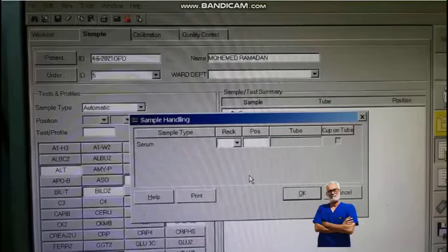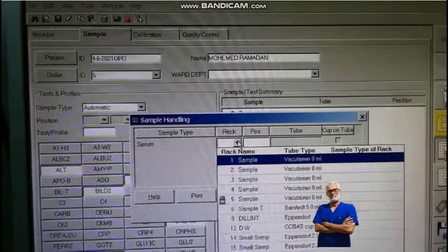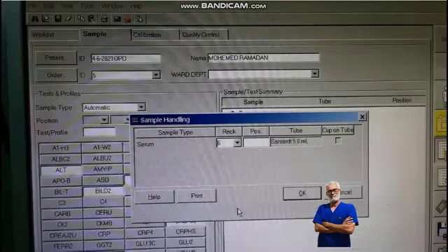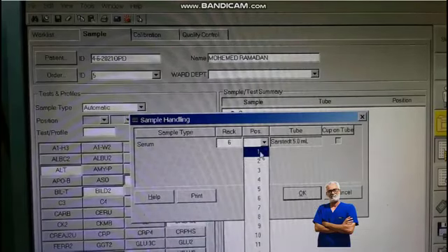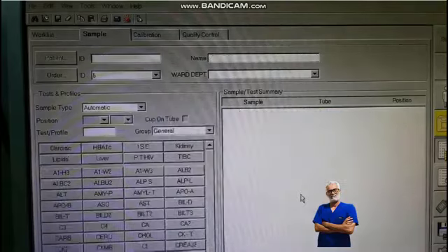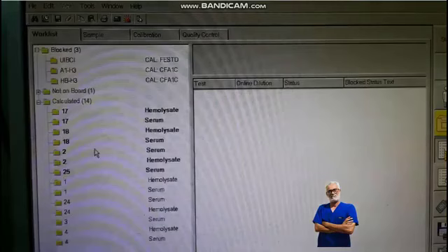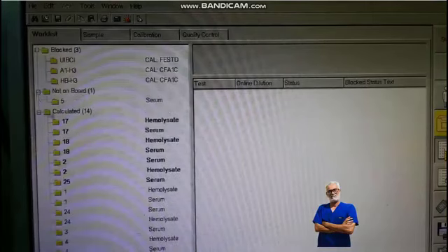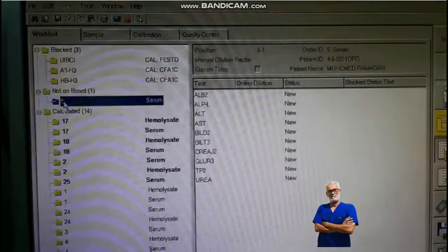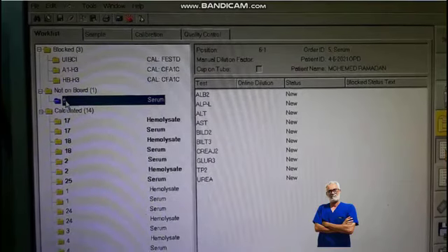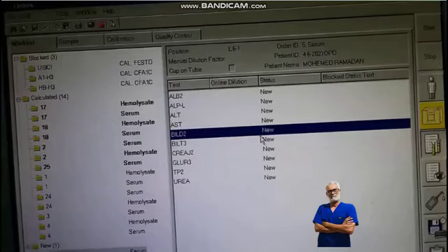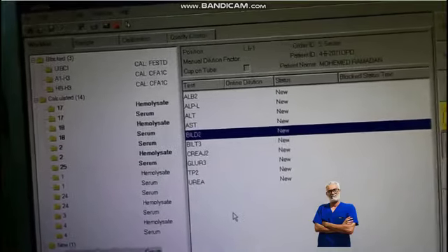While we wait for the results to be finalized, let us discuss some very important technical tips regarding the daily operation of the Integra 400 Plus. One of the most critical aspects of your work is the calibration process. You must always ensure that your calibrators are handled with extreme care. Always check the lot numbers and make sure they match the data entered into the system software. Remember, accurate calibration is the foundation of every result that leaves your laboratory.